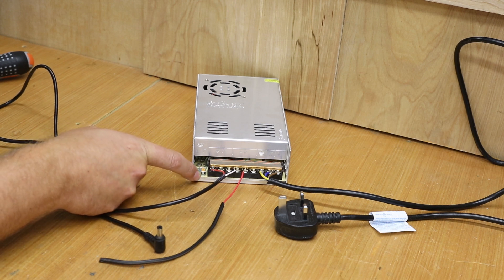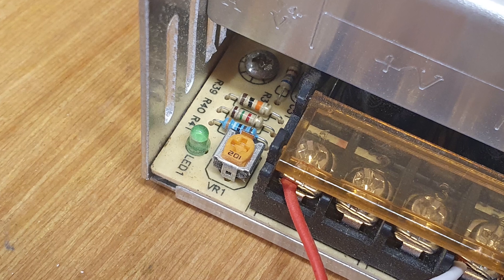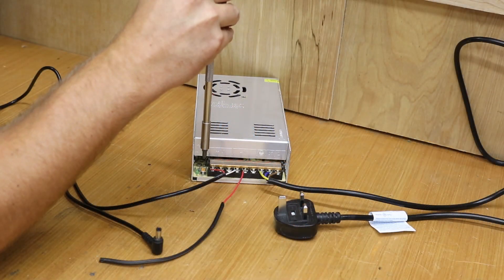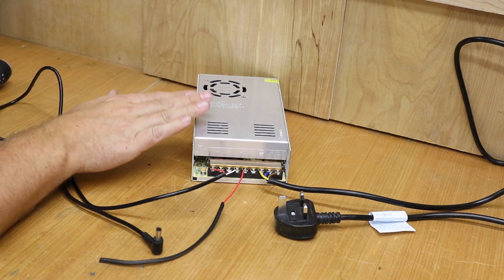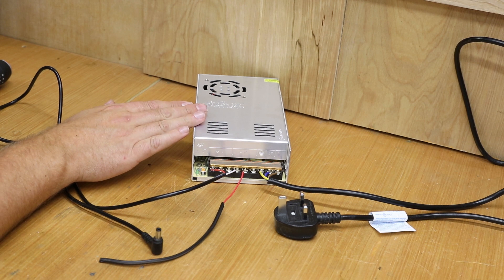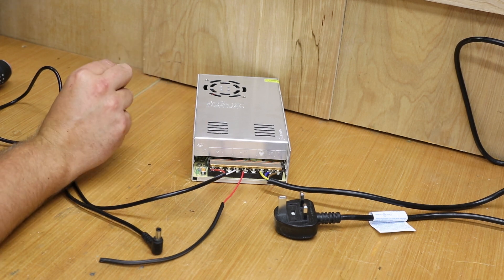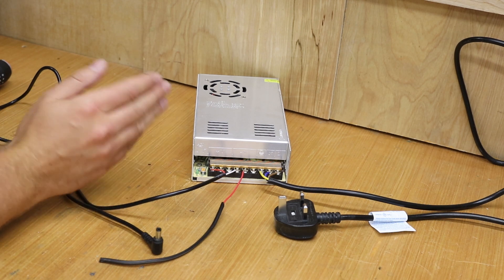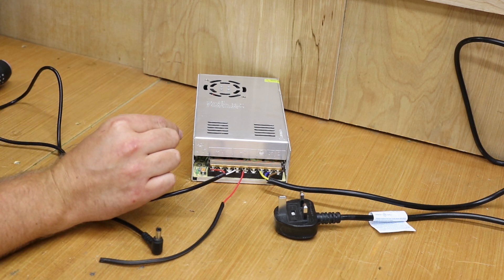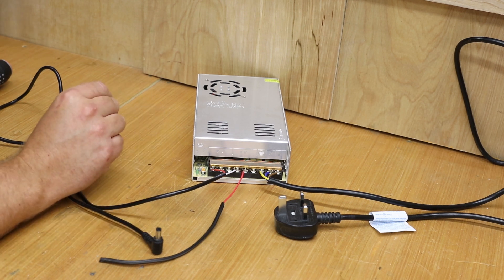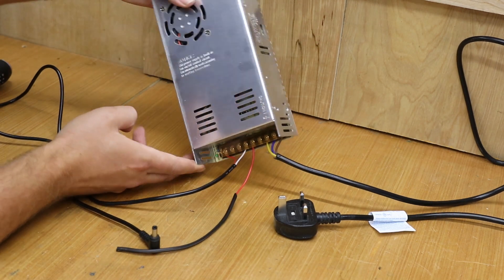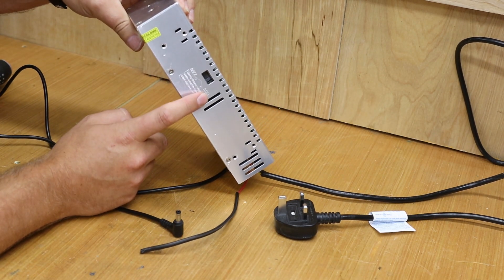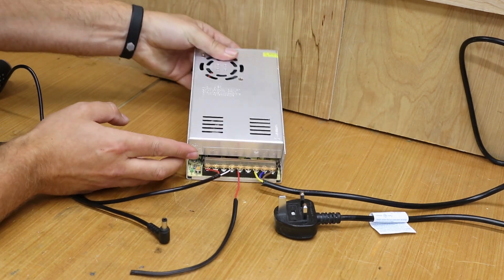At the end of the terminals you'll also see a little dial. And this dial can be adjusted by putting a screwdriver into it and turning it left or right. This dial is to control the voltage output. So even though these are a 24 volt output, they sometimes run a little bit high or a little bit low. So if you've got something like a multimeter, you can test the output of these PSUs and dial that in until you get the exact 24 volts that you're after. Now the other thing to mention on these units is they have a little switch to go from 110 volt to 220 volts, obviously depending what country you're in.